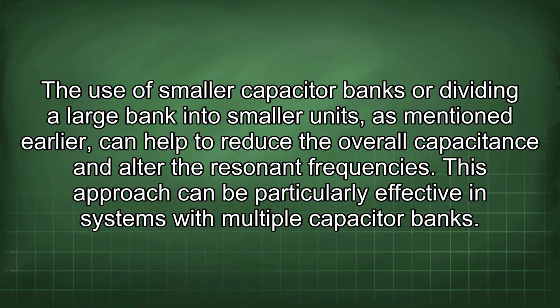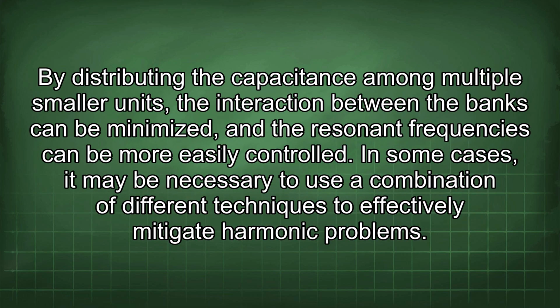The use of smaller capacitor banks or dividing a large bank into smaller units, as mentioned earlier, can help to reduce the overall capacitance and alter the resonant frequencies. This approach can be particularly effective in systems with multiple capacitor banks. By distributing the capacitance among multiple smaller units, the interaction between the banks can be minimized, and the resonant frequencies can be more easily controlled.